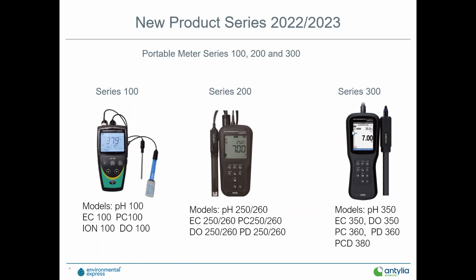The sensor has a chip built into the sensor holder or electrode head. When you replace these, you just replace the cartridge or the sensor at the base of that electrode. But the beauty is once you plug that sensor into the meter, it automatically knows, hey, this is a pH electrode, this is its serial number, this is the setup configuration that it was set up on, and the last calibration. You can even program in when the next calibration is due.